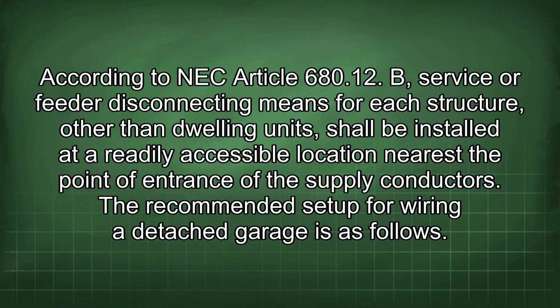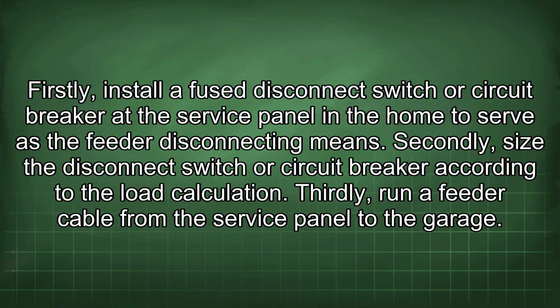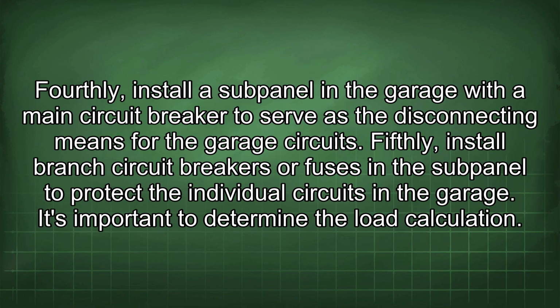The recommended setup for wiring a detached garage is as follows. Firstly, install a fused disconnect switch or circuit breaker at the service panel in the home to serve as the feeder disconnecting means. Secondly, size the disconnect switch or circuit breaker according to the load calculation. Thirdly, run a feeder cable from the service panel to the garage. Fourthly, install a subpanel in the garage with a main circuit breaker to serve as the disconnecting means for the garage circuits. Fifthly, install branch circuit breakers or fuses in the subpanel to protect the individual circuits in the garage.